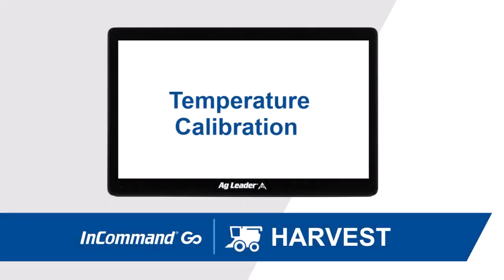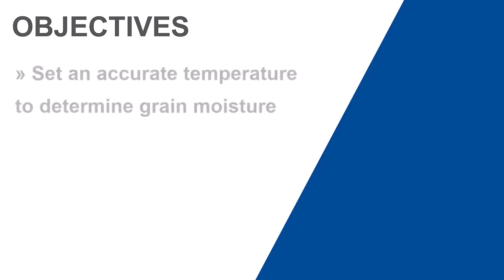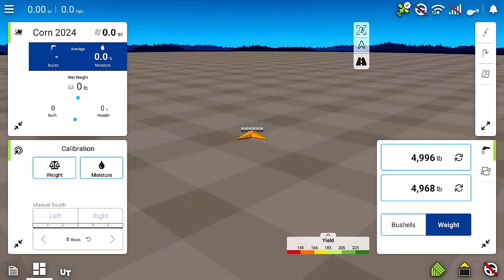In this video, we will cover how to perform a temperature calibration. It is key to have an accurate temperature reading to be able to accurately measure the moisture of the grain. Temperature calibrations need to be performed before the moisture calibration. Temperature calibration will only need to be performed once.